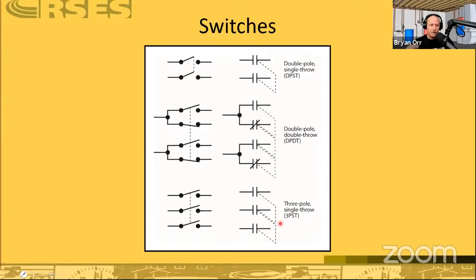That's what we call single phasing. So in 3-phase applications, you're always going to break all three legs. I say always, but there's always some exception to always that I'm not thinking of, and somebody will point out the one thingamajig that doesn't. But anyway, you've got to break all 3 because you don't want to single phase, you don't want to run on just 2 legs.